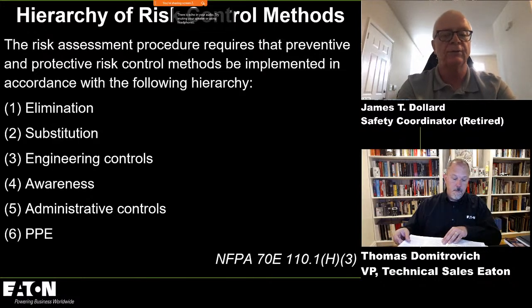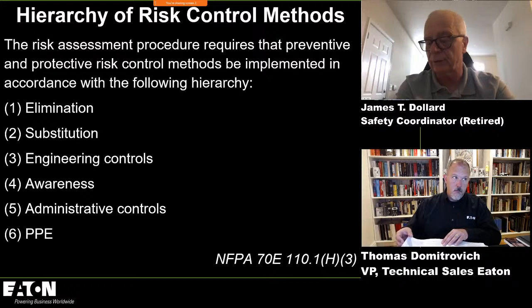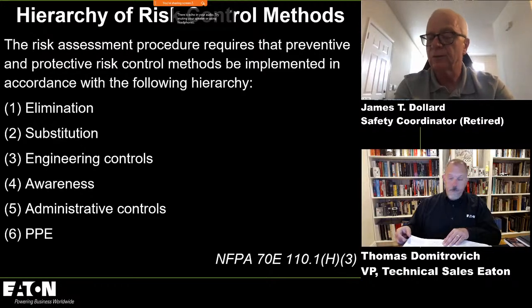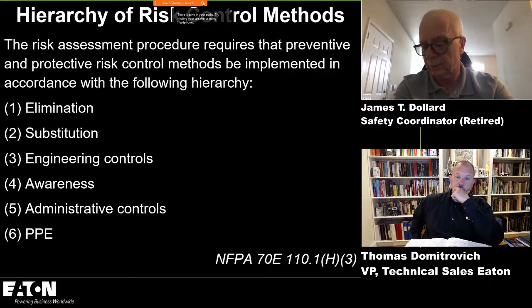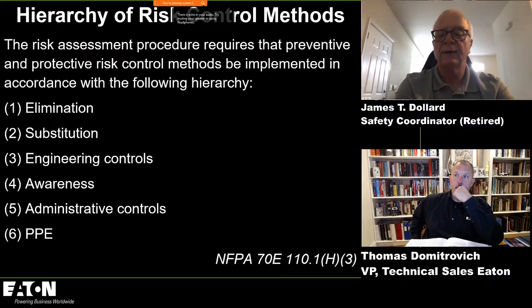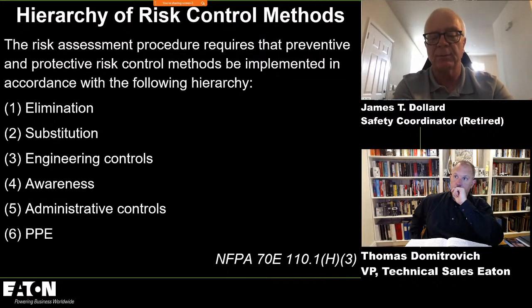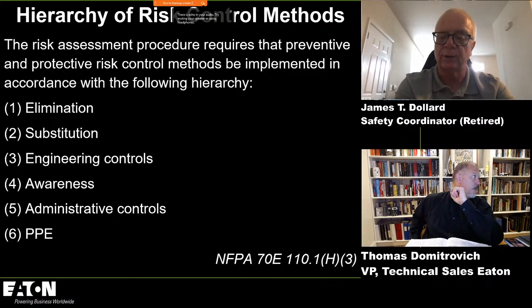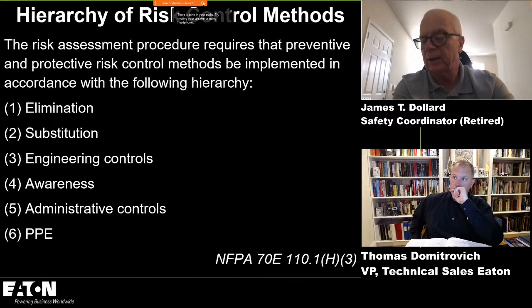And ANSI Z10 solved them as elimination, complete elimination, 24/7, 365. So how do you eliminate a source of voltage in an electrical distribution system 24/7, 365? You cannot. It's impossible. So we've got informational notes now to explain that elimination is the creation of an electrically safe work condition. But we'll get there in a little bit. You have to remember that the act of creating an electrically safe work condition is actually energized work. So that's elimination. Substitution is very easy, but it lends itself well to design.